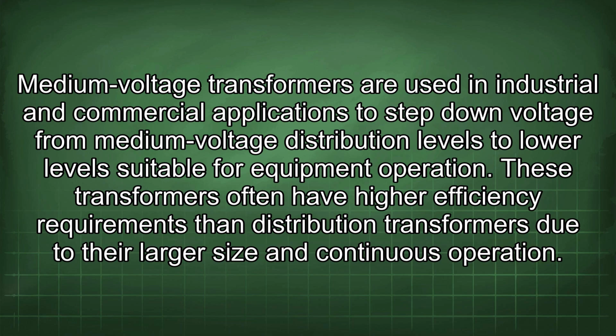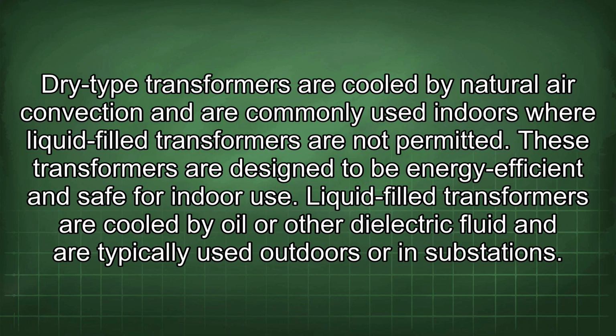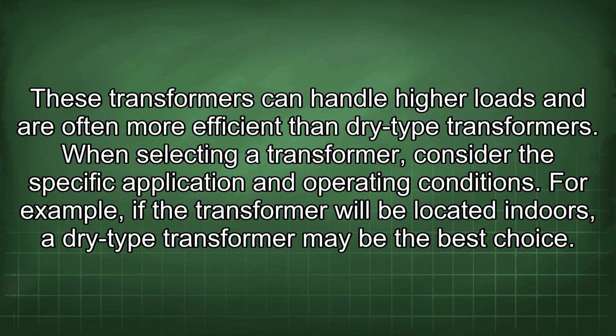These transformers often have higher efficiency requirements than distribution transformers due to their larger size and continuous operation. Dry-type transformers are cooled by natural air convection and are commonly used indoors where liquid-filled transformers are not permitted. These transformers are designed to be energy efficient and safe for indoor use. Liquid-filled transformers are cooled by oil or other dielectric fluid and are typically used outdoors or in substations. These transformers can handle higher loads and are often more efficient than dry-type transformers.